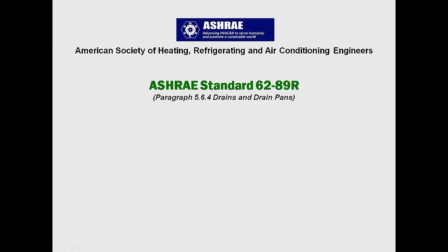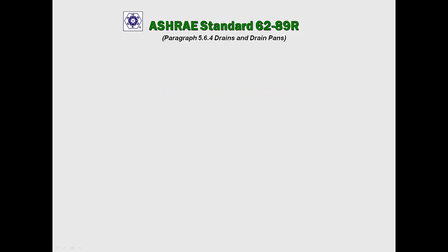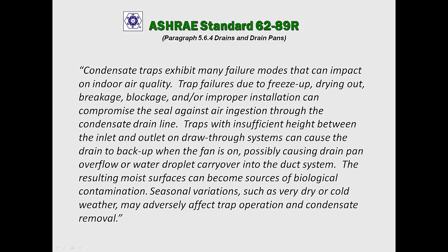Many of these critical failure modes were identified by ASHRAE in their standard 6289-R, which discusses drains and drain pans in paragraph 5.6.4. What ASHRAE standard 6289-R says about condensate traps is quoted as follows: Condensate traps exhibit many failure modes that can impact on indoor air quality. Trap failures due to freeze-up, drying out, breakage, blockage, and/or improper installation can compromise the seal against air ingestion through the condensate drain line. Traps with insufficient height between inlet and outlet on draw-through systems can cause the drain to back up when the fan is on, possibly causing drain pan overflow or water droplet carryover into the duct system. The resulting moist surfaces can become sources of biological contamination. Seasonal variations, such as very dry or cold weather, may adversely affect trap operation and condensate removal.